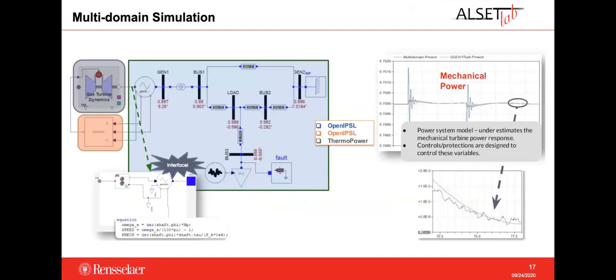This other application shows how we can leverage the Modelica environment to perform multi-domain simulation. The gas turbine, which is usually represented by a couple of time constants in most power system modeling tools, is here modeled in detail using the ThermoPower Library — also a Modelica library. We take advantage of an existing Modelica library to represent part of the system in a more detailed view; we just need to create an interface between them.